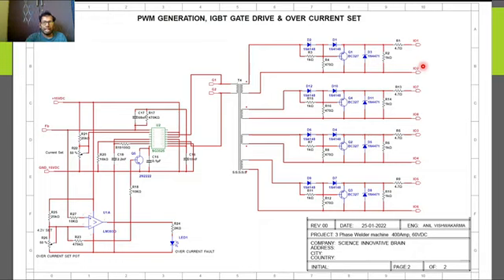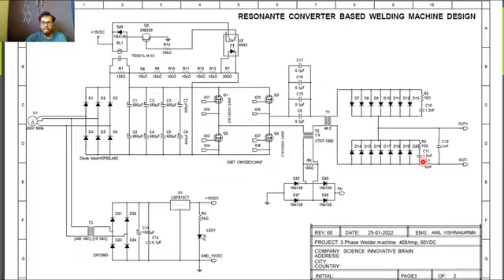At the same time, if the pulse is reversed and this is fired while that is not turned off, then shoot-through will happen across this and the IGBT will get damaged. So to avoid this...